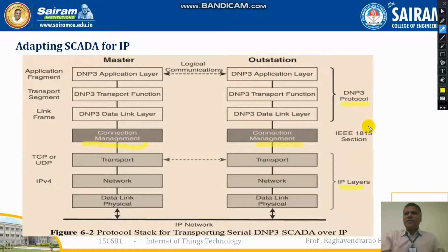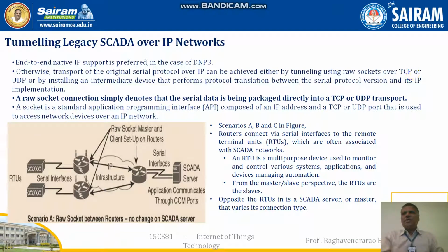Now, the tunneling legacy SCADA over IP, the end-to-end connection, how that happens. Here the end-to-end native IP support is preferred in the case of DNP3. Otherwise, transport of the original serial protocol over IP can be achieved either by tunneling using raw sockets over TCP or UDP, or by installing an intermediate device that performs protocol translation between the serial protocol version and its IP implementation.